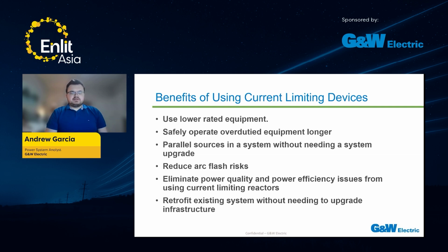You can parallel sources in the system without needing a system upgrade. So say you have two separate switchgears, large switchgears, that you want to connect via bus tie to either increase your system capacity or increase reliability. You can then install a current limiting device in that bus tie between the two now connected gears to make sure that both those gears are now properly rated, since the gear would not be initially designed to be connected like that. Ultimately, these devices are also great at reducing arc flash risks and hazards. Last but not least, you don't have to worry about any power quality issues via voltage drop, and you can save some money via increased power efficiency from using these devices, any of these devices other than current limiting reactors.